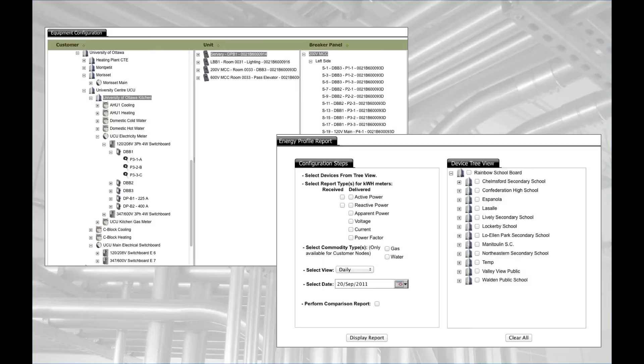The cloud-based PowerHawk Manager generates an installation record for the contractor to wire into the panel, using color coding for proper circuit association. Once the CTs are wired, the contractor simply plugs the cable into the meter. The installation record also serves as a permanent record, both in the database as well as affixed to the electrical panel, for traceability and, if required, future troubleshooting or moves, adds, and changes.